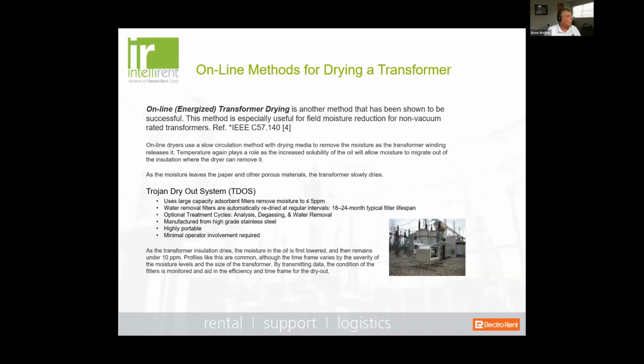May or may not be accurate, but one of the things that we found, and we rent this piece of equipment quite often, it's an online drying system. Basically it is a device that connects to the transformer while it's online, and then filters the moisture automatically out of the oil itself. Now, what's the difference? Well, the difference is that you're doing this drying process while the transformer's online at the operating temperature. And as it draws the moisture out of the oil, it's also pulling it out of the insulation.